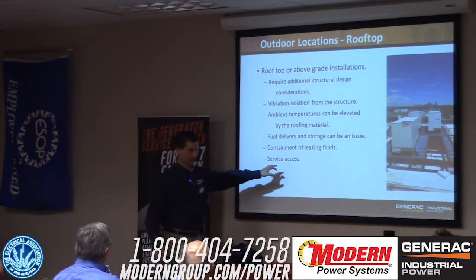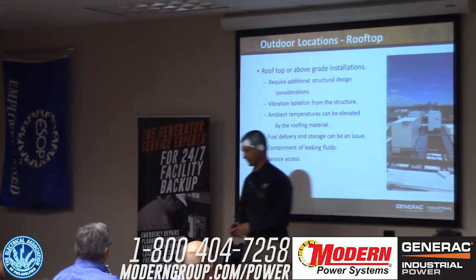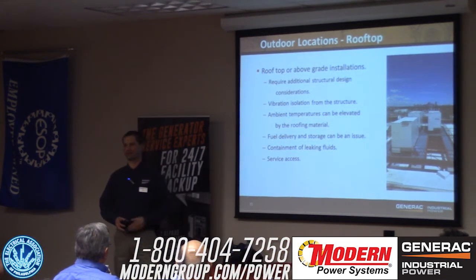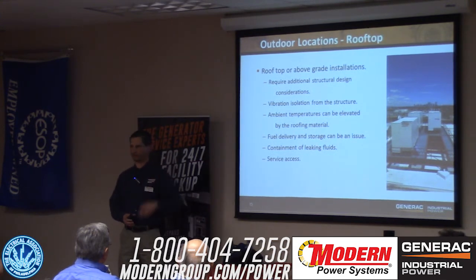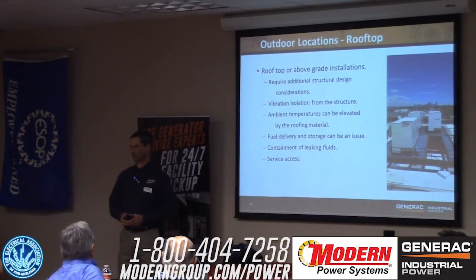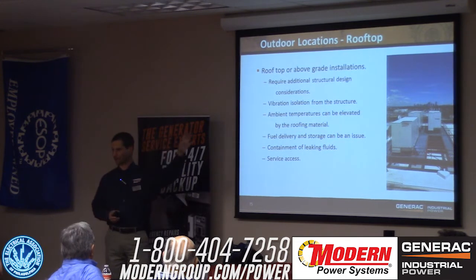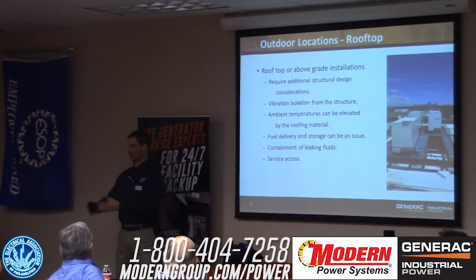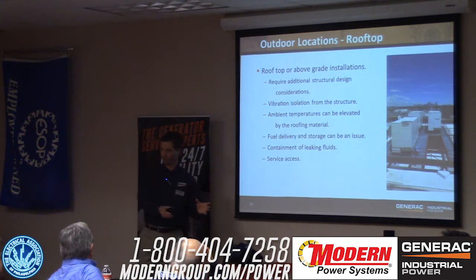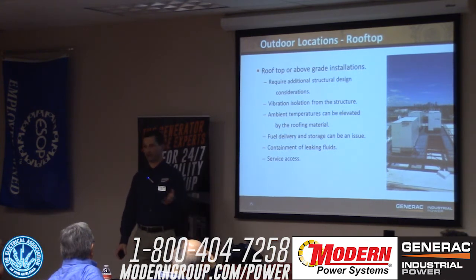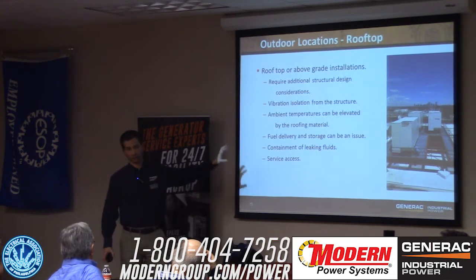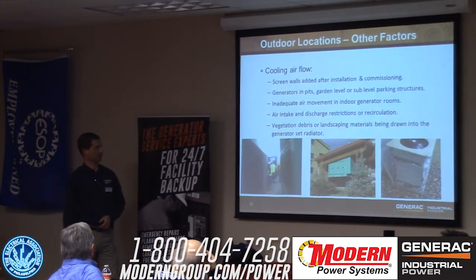Service access - and I don't mean access around the machine so much as what agreement the servicing contractor or distributor has with the building management. If you're not there at 2 a.m. on a Sunday and the machine goes down, do you have to go there? Is there an arrangement where the generator service vendor can get to the machine by himself? This is a consideration that has to come into the planning, more with the owner. It's kind of after it's left our house - our responsibility has ended, but as you're talking design with your clients, what are we going to do to get the service guy up here if nobody's in the building?